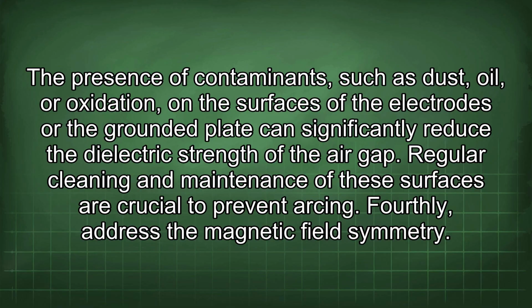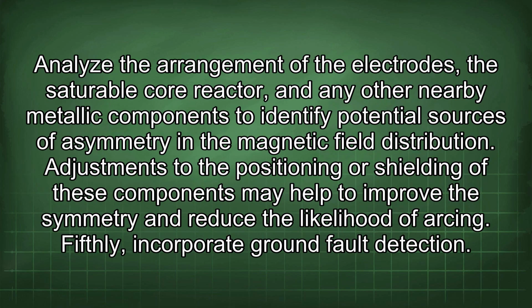Fourthly, address the magnetic field symmetry. Analyze the arrangement of the electrodes, the saturable core reactor, and any other nearby metallic components to identify potential sources of asymmetry in the magnetic field distribution. Adjustments to the positioning or shielding of these components may help to improve the symmetry and reduce the likelihood of arcing. Fifthly, incorporate ground fault detection.